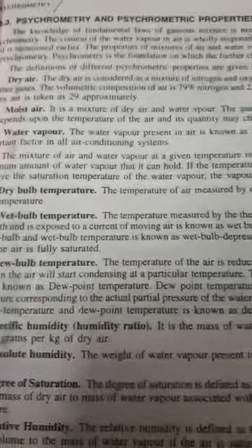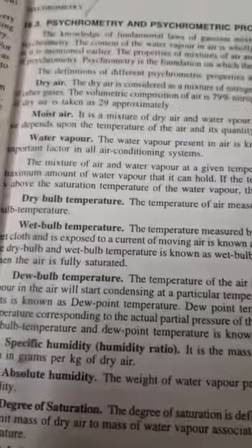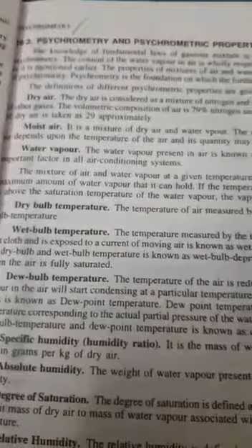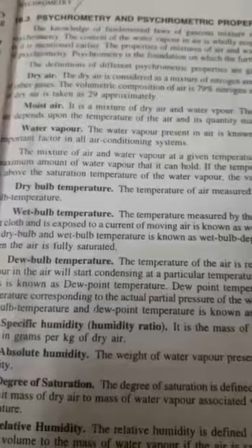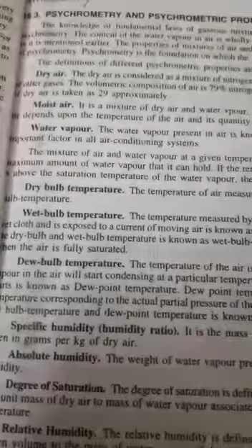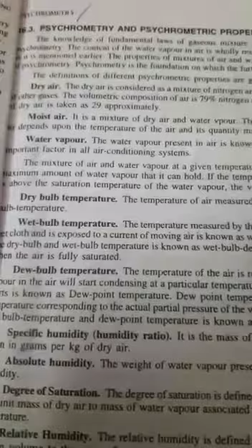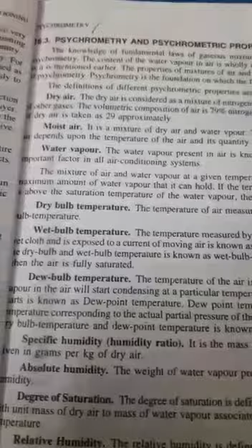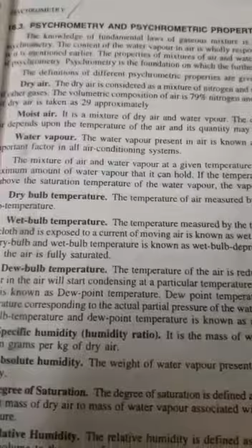For the wet bulb, there will be a small wick, and the wick will be dipped in a small plastic bottle consisting of water. So when the water comes through the wick up to the bulb, it gets evaporated according to the condition of the place. Suppose you are keeping the dry bulb wet bulb thermometer in Hyderabad, which has dry conditions. So the moisture gets evaporated faster into the air, thereby taking the heat from the bulb itself. That means the wick gets dried up faster and it takes the water from the plastic bottle.